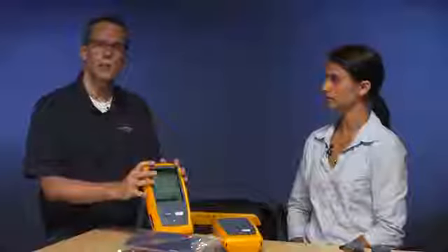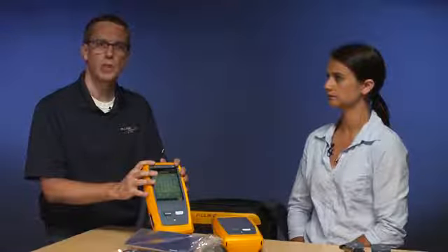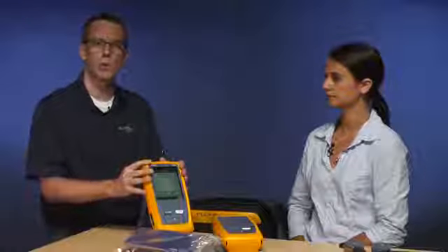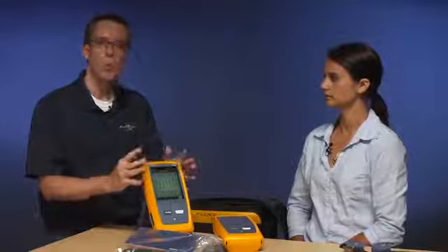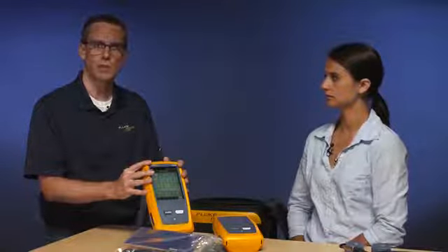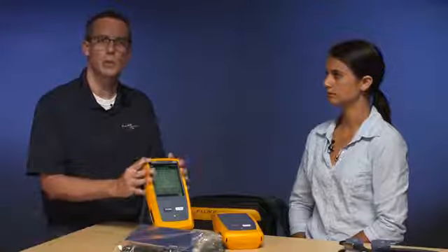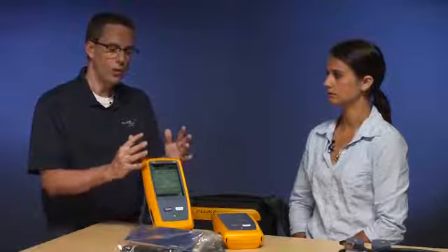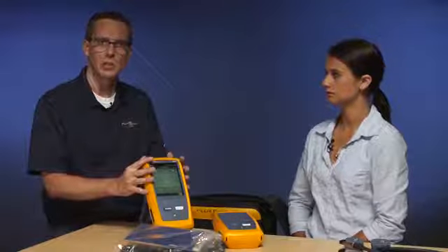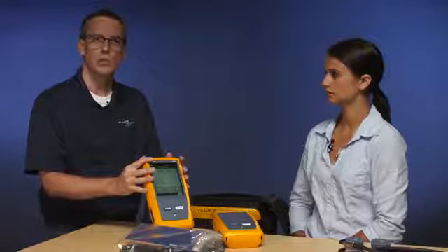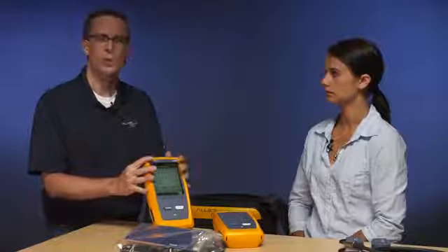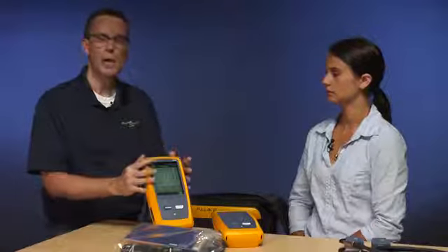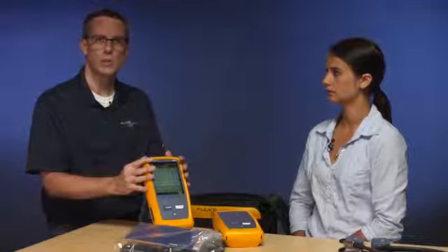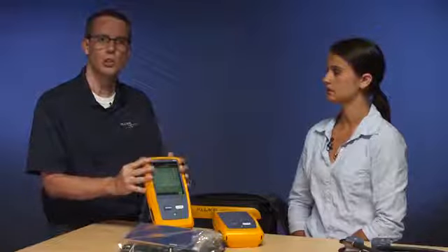When it arrives, it's probably going to have about 35% charge in it. Now I've charged it fully today just for this shoot here. We're not allowed to ship this from the factory fully charged. I wish we could, but we're not allowed to. So don't forget to plug this in. From a 0% battery status, expect 4 hours to charge it up to 100% with the instrument off. If you've got the instrument powered on, it's about 6 hours, so you can charge and use this instrument at the same time.